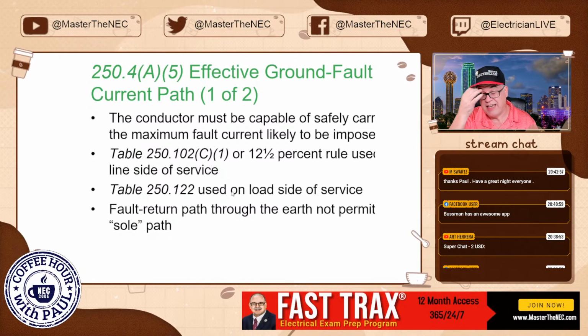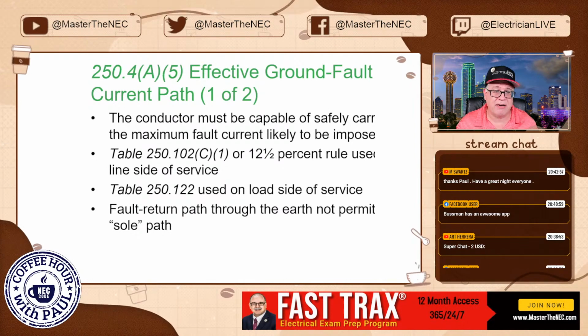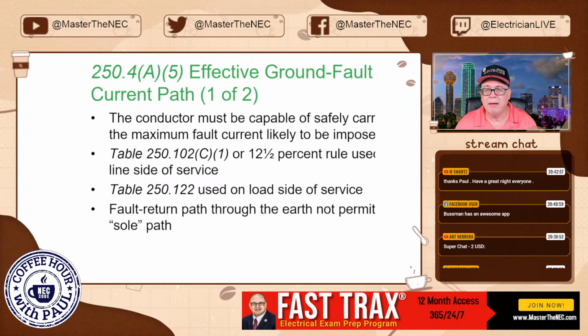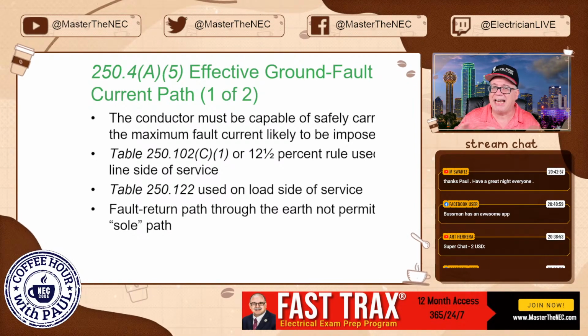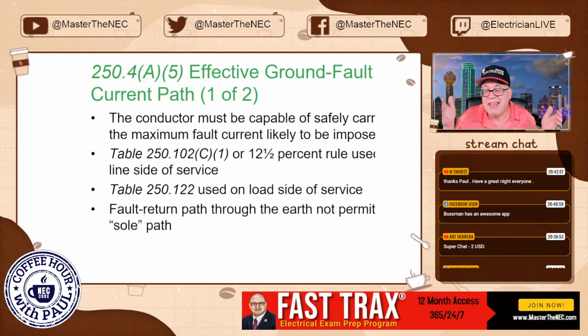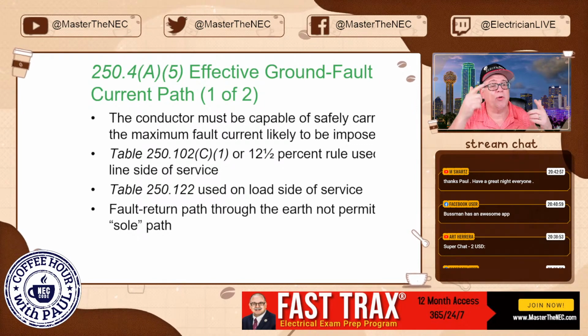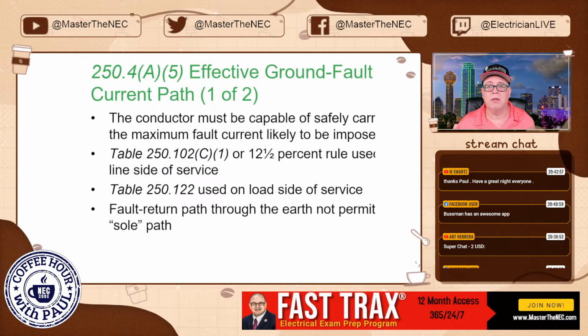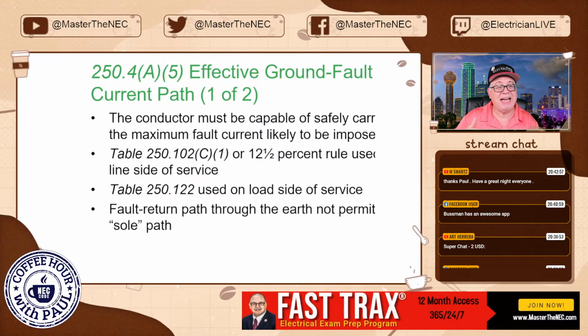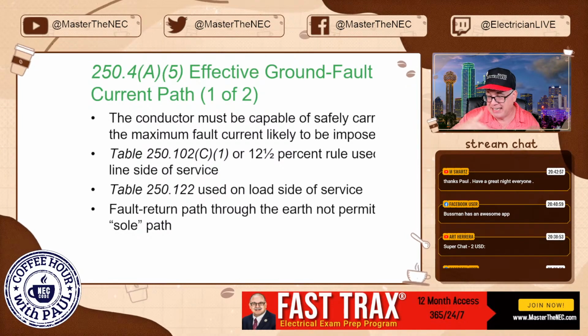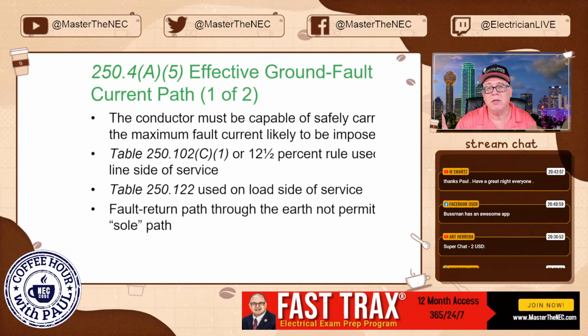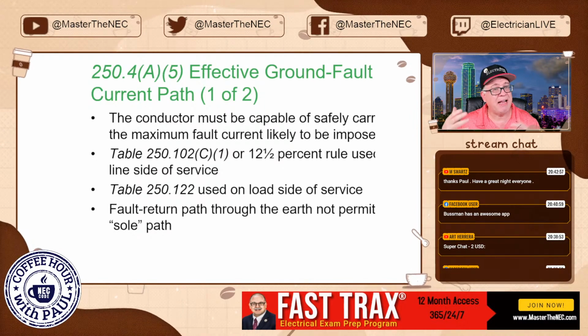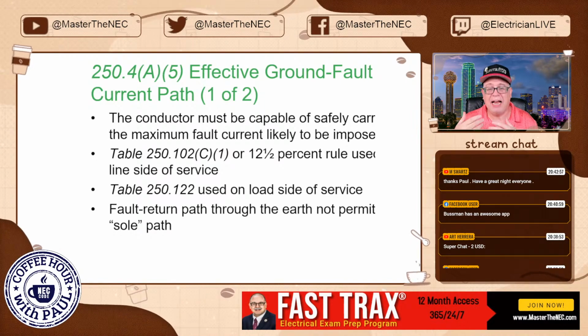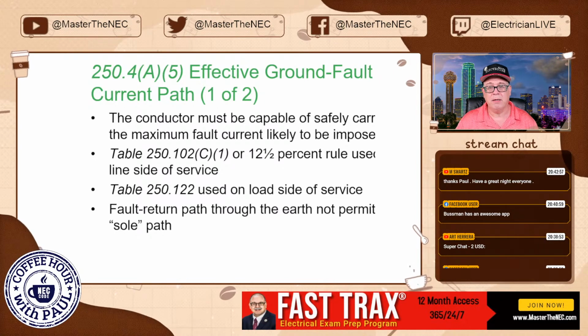So what that means is, yeah, you're going to have multiple connections that might connect to earth, but you cannot rely on that as your return path. It might be there. You might have multiple grounding points on a system, right? Like, for example, I might have a detached structure, and that detached structure has to have a grounding electrode system, but I'm running a feeder out there. But my service for the house has a grounding electrode system, right?